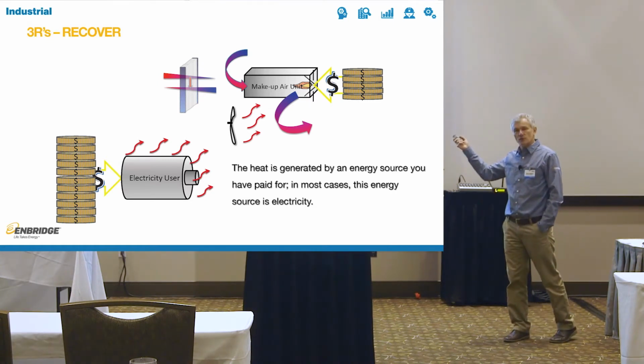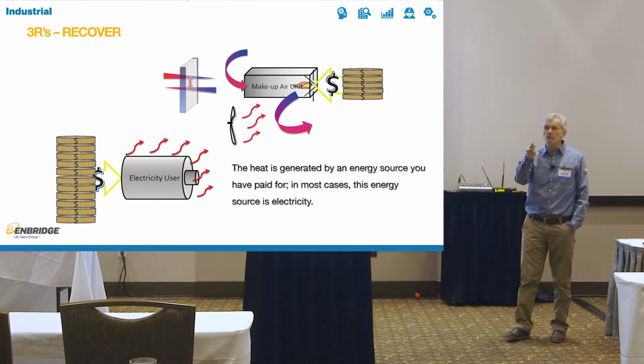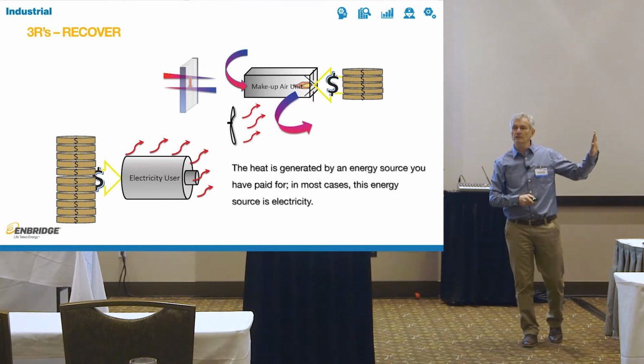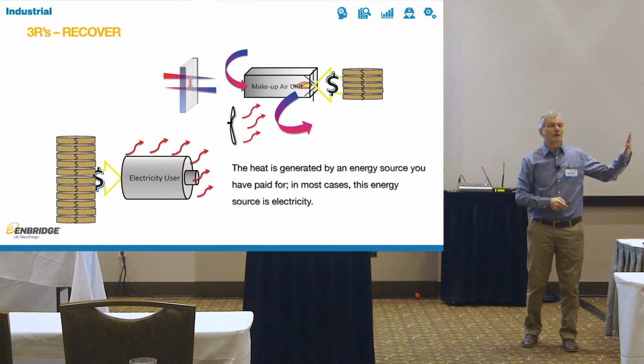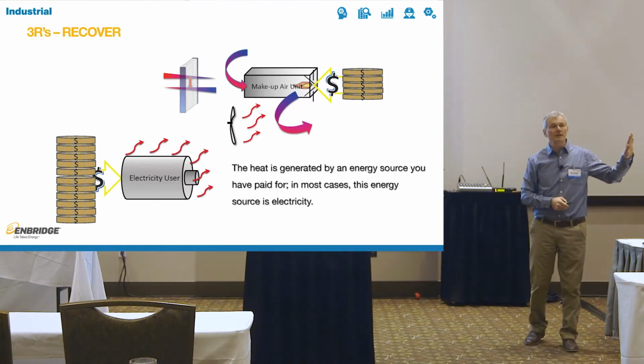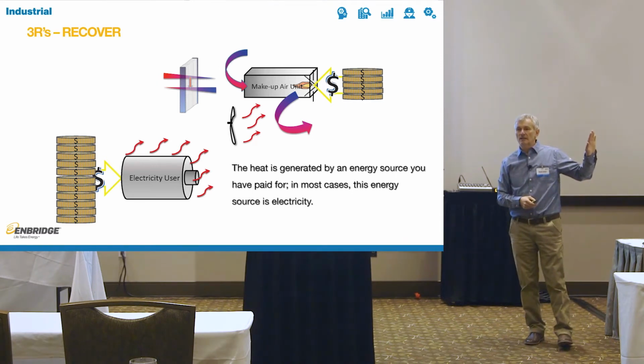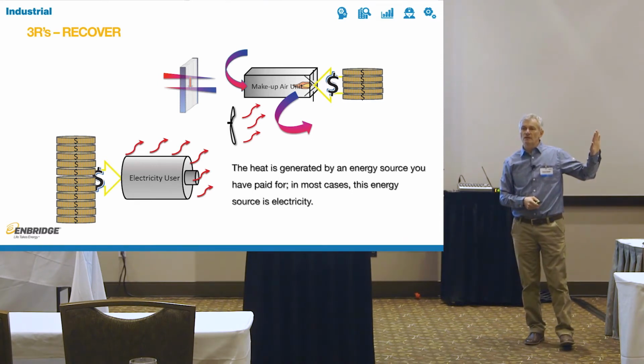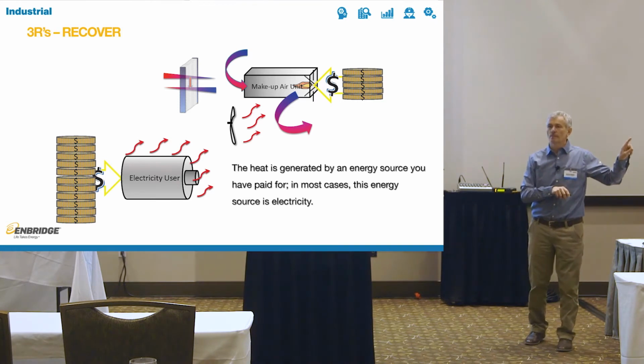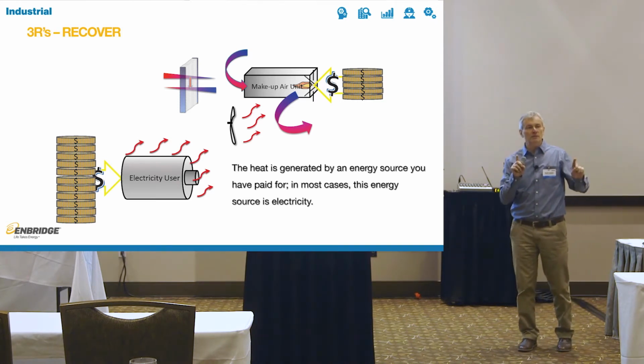So you have a whole bunch of electricity users. Has any one of you ever stood next to the bank of VFD drives, the panel? You notice how warm it gets? That's because when you use a VFD and you throttle it down, guess where the energy is going? In the friction, it gets tossed into heat and gets tossed out. So VFD is not inexpensive. It's not cheap. And it's not free.